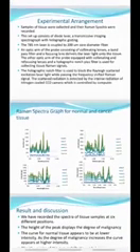The other optic arm of the probe, equipped with collimating and refocusing lenses and a holographic notch plus filter, is used for collecting tissue Raman signals. The holographic notch filter is used to block the Rayleigh scattered excitation laser light while passing the frequency shifted Raman signals. The scattered radiation is detected by an intensified, nitrogen-cooled CCD camera, which is controlled by a computer. Here, the Raman spectra for 4 different tissues are shown.